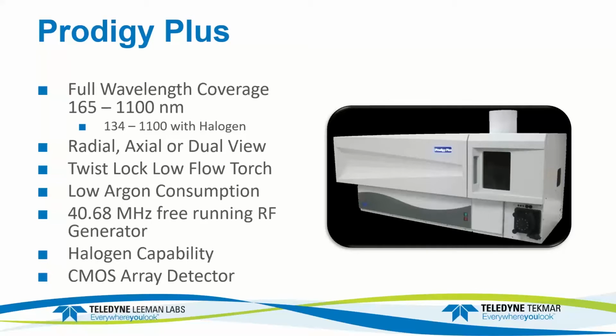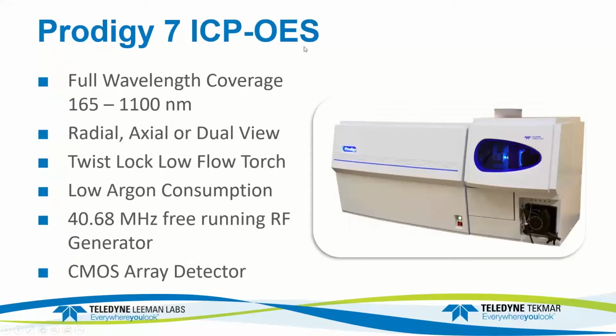We also manufacture the Prodigy 7 ICP, which is very similar to the Prodigy Plus, does not have the halogen capability, and has a little bit smaller form factor. The data was collected on the Prodigy Plus, but a Prodigy 7 is equally as capable in this particular application. We used the Prodigy Plus because it was a radial view system that we had, but the sample introduction part of the instrument and the software that runs these instruments are identical.